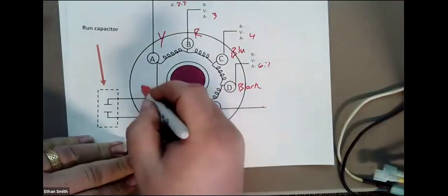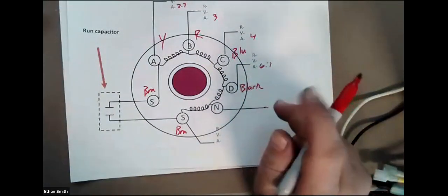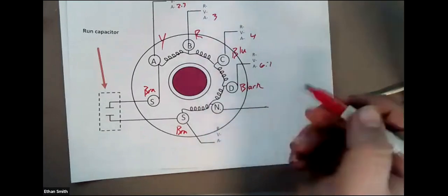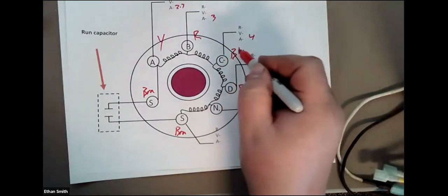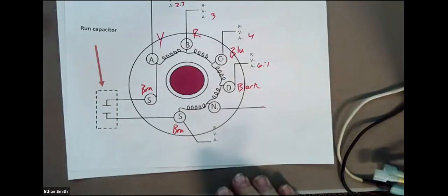Because your start is always going to be down there. What happens if you put your run on the one that's below it? These are brown here, and those are brown, black. I think something different would happen if you put it on black versus on red or yellow. So we're always going to have 2 wires connected. What I'm proposing is we take our neutral and move it to the C terminal, which is the blue wire, and keep our power wire on black. It'll run backwards.